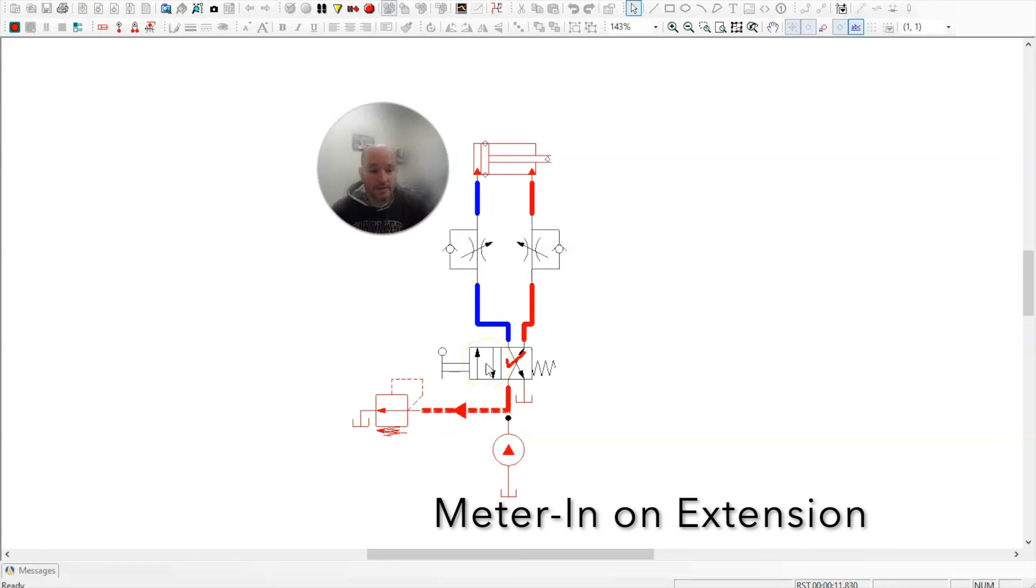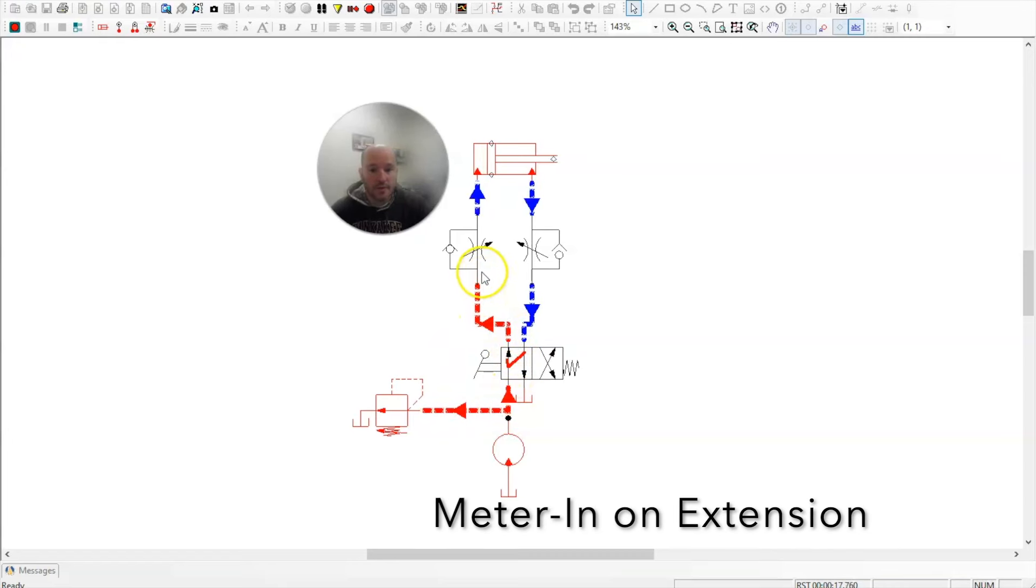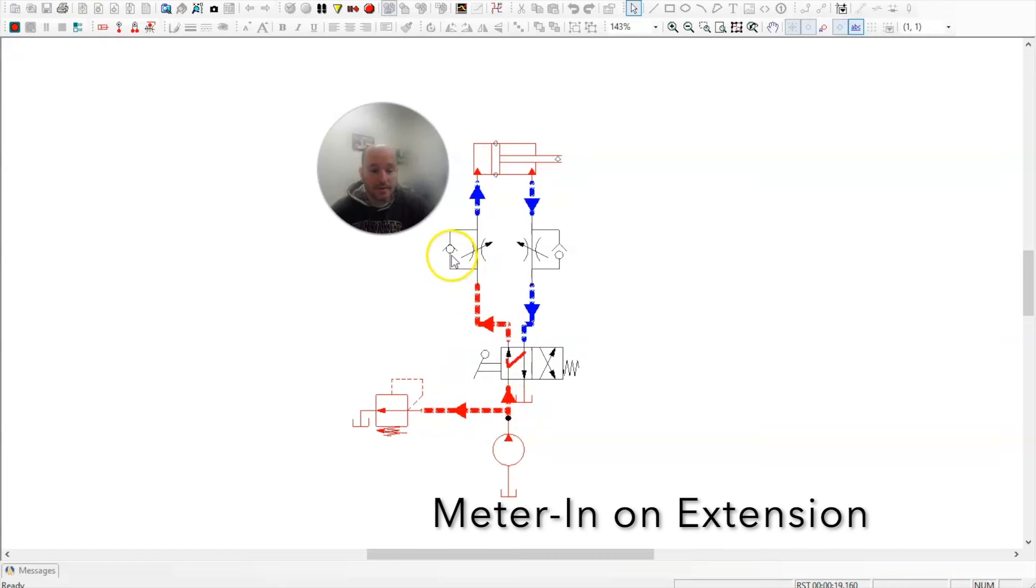When I activate the directional control valve, oil flows up through here. It cannot get through the bypass check valve, so the oil is metered or the flow is controlled while it's going into the cylinder during extension. This would be metering in on extension, and you can see it goes slow.